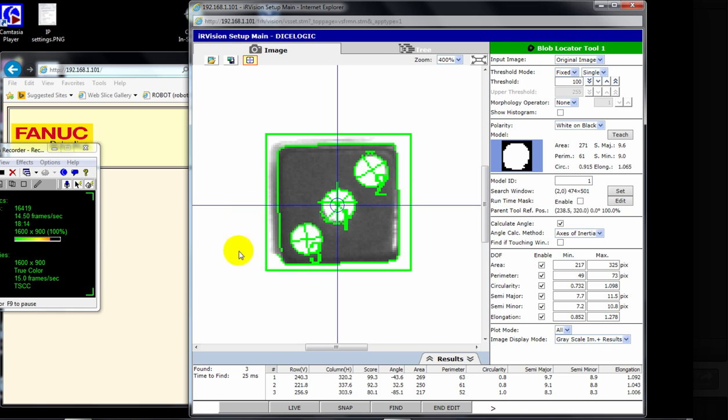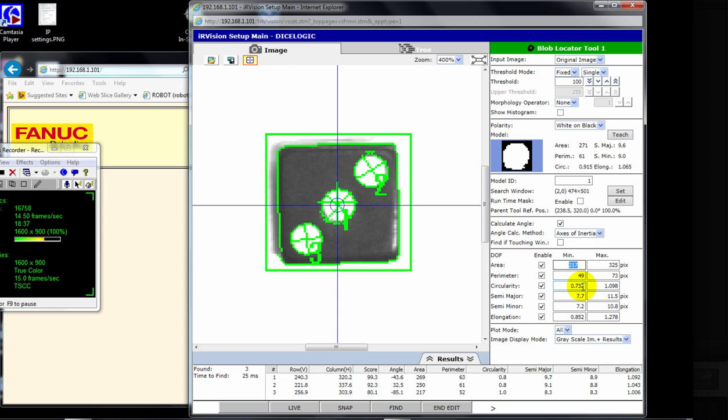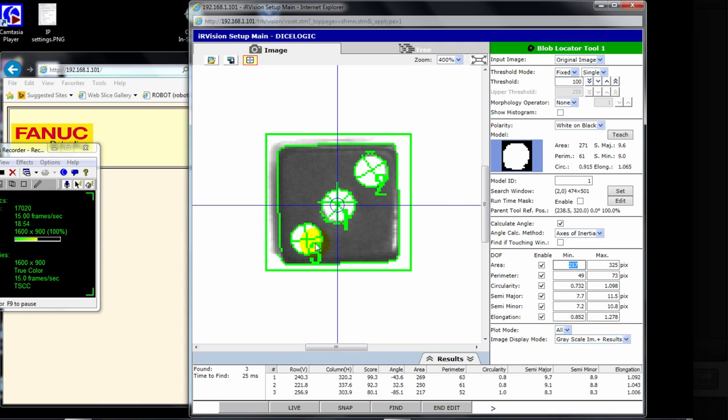So I came back and did a snap, find, within the blob tool, and I found all three. But if you look at the area, that is real close to the minimum value here. So I'm going to bump this guy down. That's probably why it didn't find it within my complete process. As the process went down and found the GPM and then looked for the blobs, this number three, for the first time, they're never the same. You know, every two run vision finds are going to find different results. And it didn't, it probably bumped below 217. So I'm hoping that if I set this down to 210, it'll be more forgiving and find it. In fact, I'll go to 205.